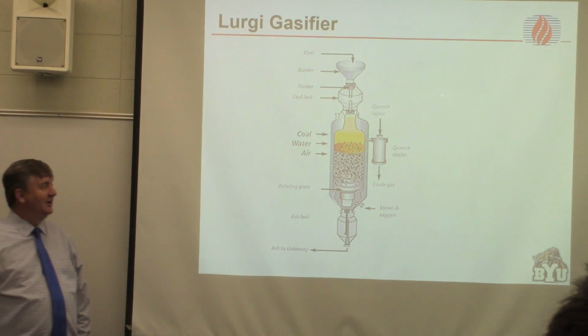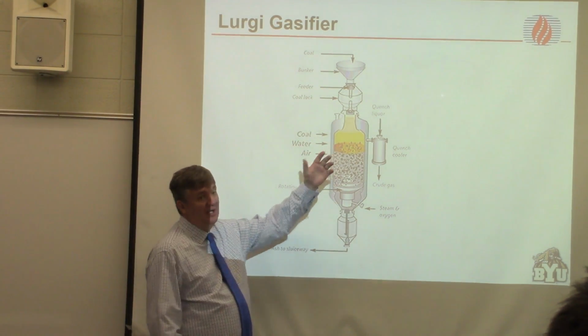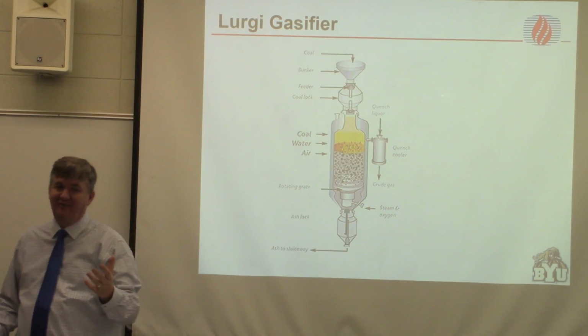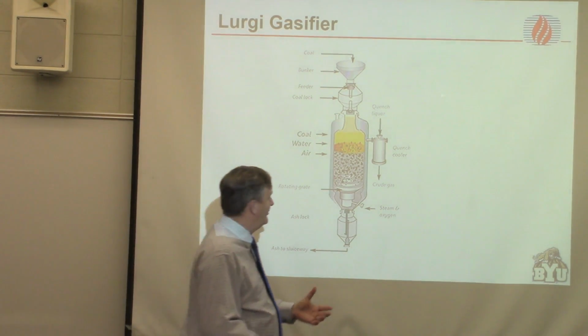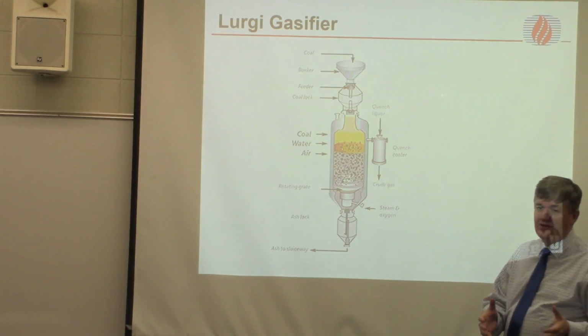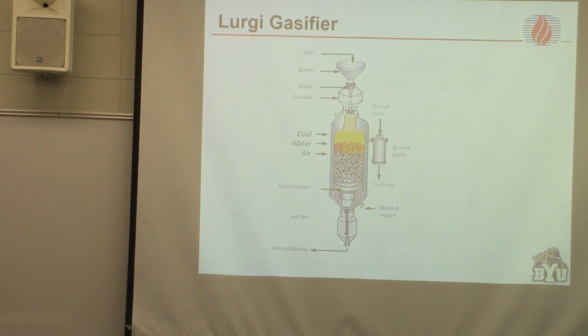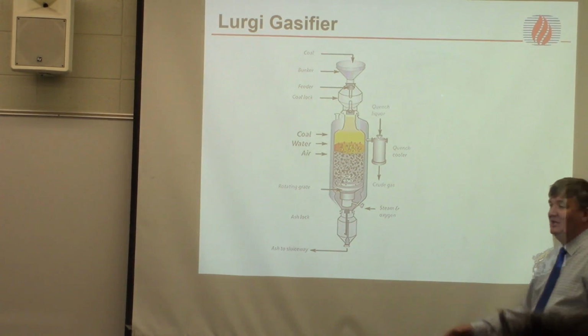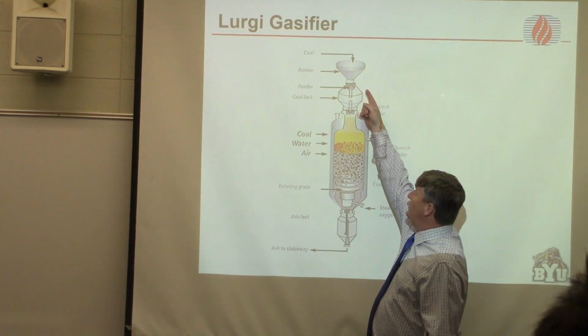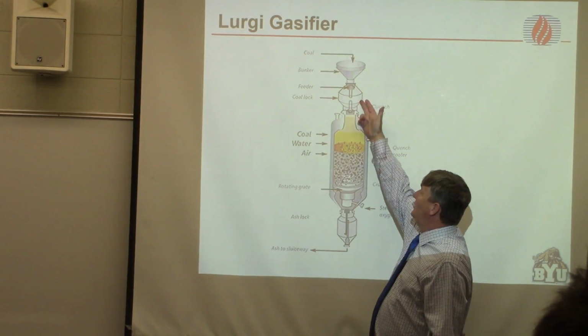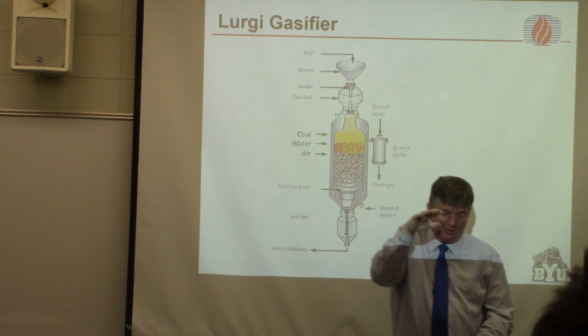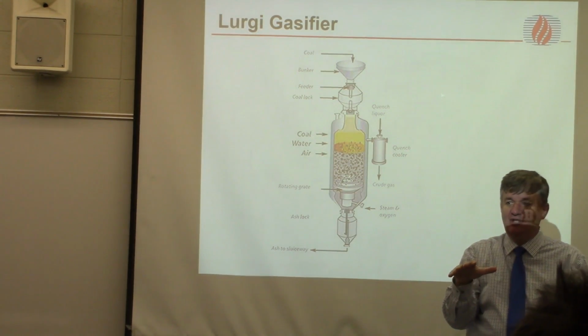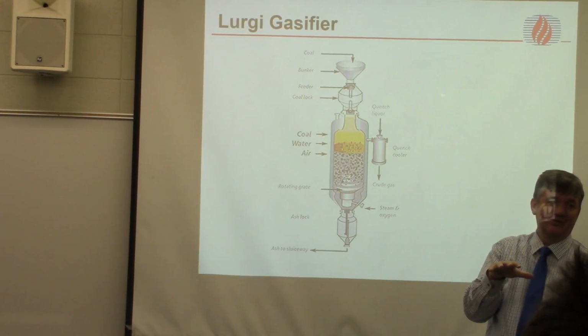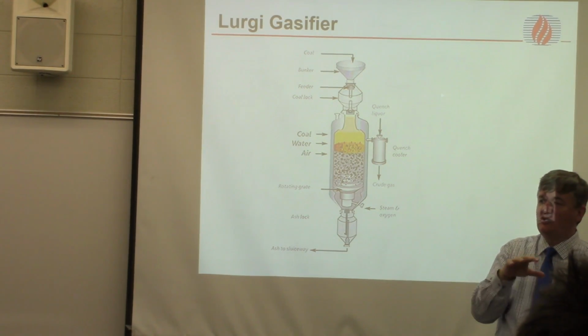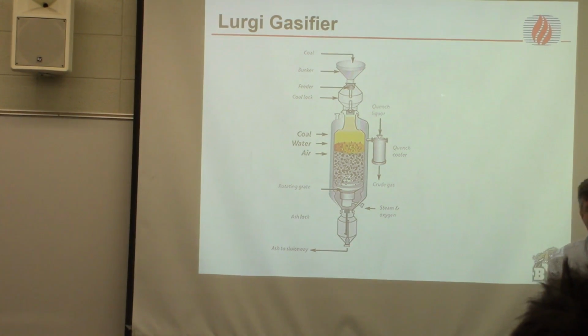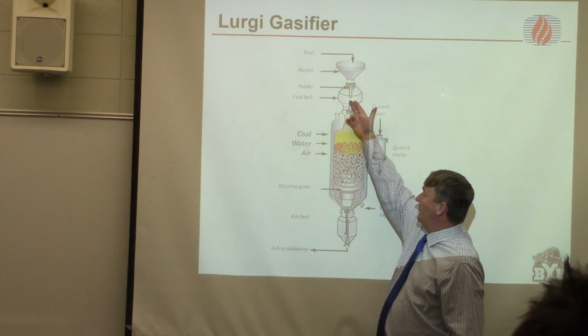This is the original kind of gasifier that people use. Gasification has to happen at pressure to make it effective, at least with coal. So you have to have a pressure vessel, and feeding coal into a pressure vessel is a hard thing to do. Feeding a liquid into a pressure vessel is not so difficult, but feeding a solid into a pressure vessel is tough. So you feed coal through here, you go through what's called a lock hopper, where the coal drops into a small chamber, and you seal it and pressurize the chamber, and then the bottom of the chamber opens, and it's now pressurized and goes into the pressure vessel, and you just keep doing that, kind of like the pressurized chambers that you get on and off submarines through.